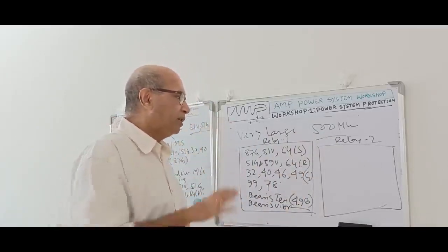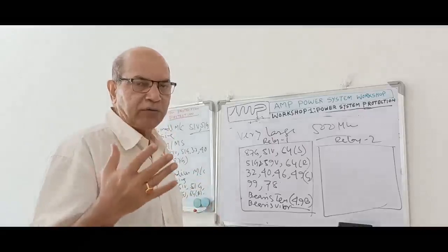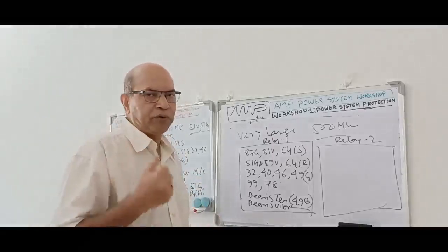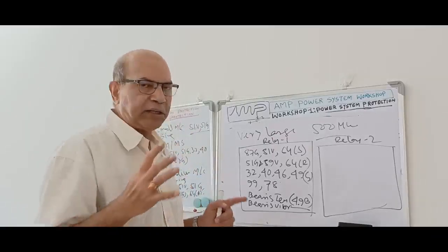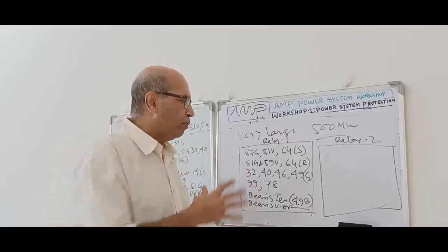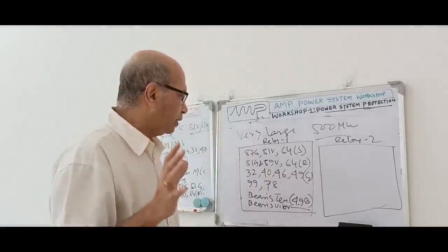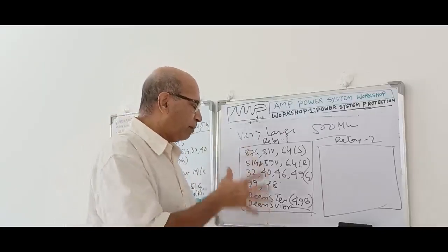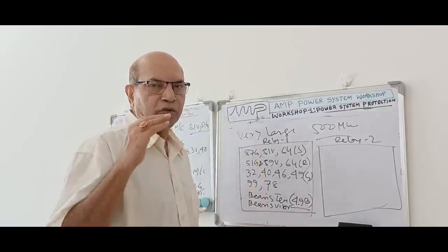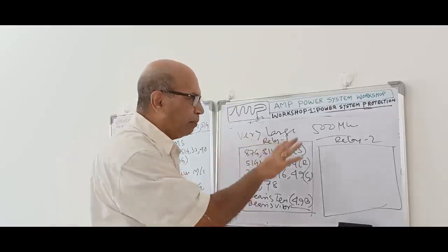This is, more or less, the guideline for this. But case to case, we can evaluate with the new approach for the protection. And now, as the digital multifunction relay is available nowadays, we need not go to discrete relays. Only maybe differential protection needs a separate set of relay, but all other protection functions we can put in the one relay, and through the algorithm and calibration we can make the protection function.